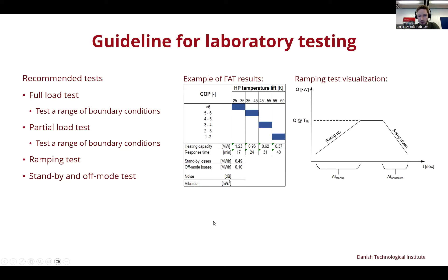Then we also recommend a ramping test where you measure the startup and shutdown time, as the energy spent during ramp up and shutdown is mostly wasted energy and is important for calculating, for example, seasonal COP or the OPEX of the system. And then we also recommend standby and off mode tests, which are intended to measure the electrical power consumption when the heat pump is not operating. And such a test result could be shown as in the table here below, where you have different temperature lifts of the heat pump and the resulting COP and heating capacities, and also the standby losses.